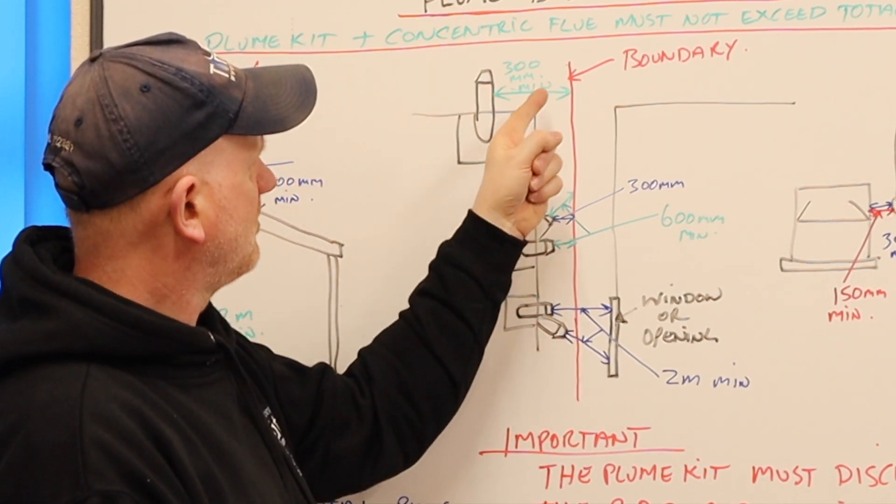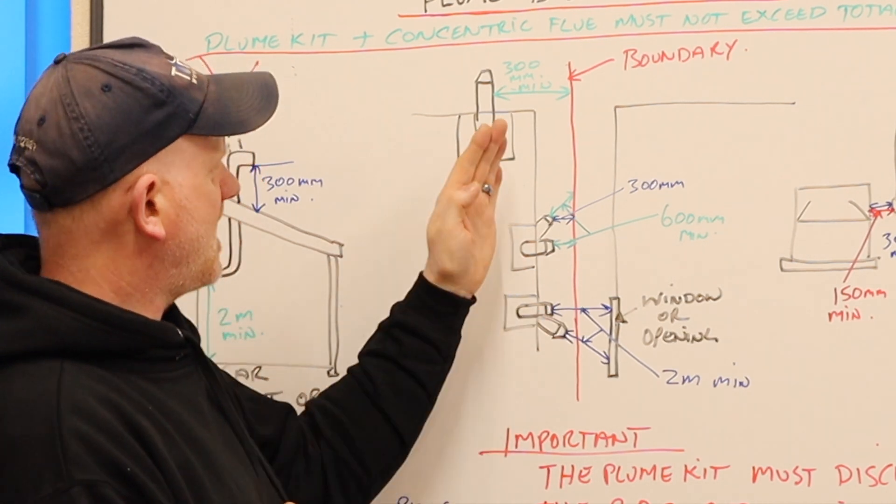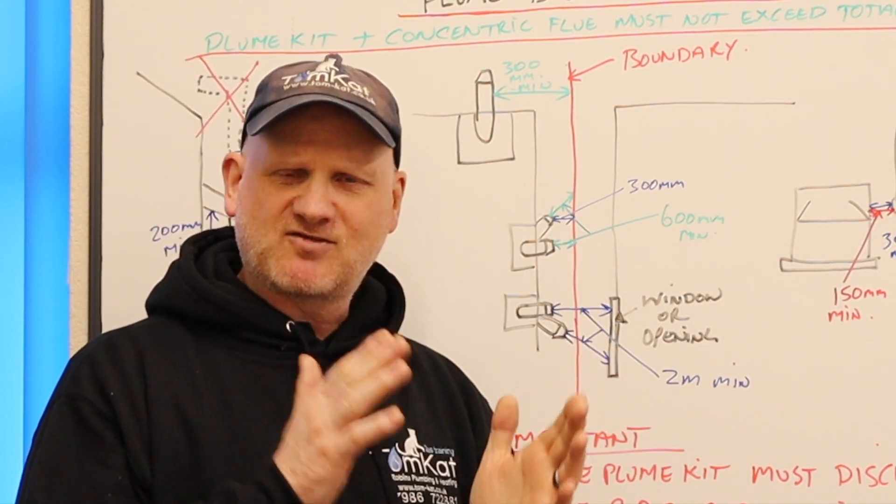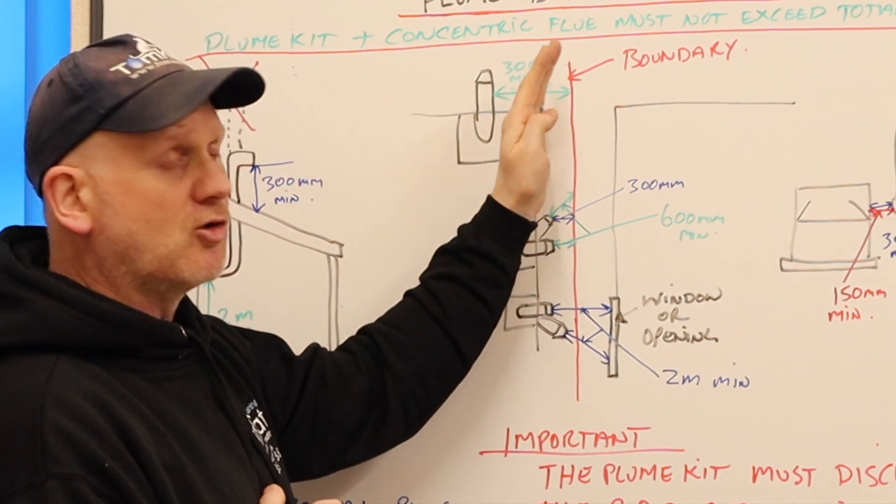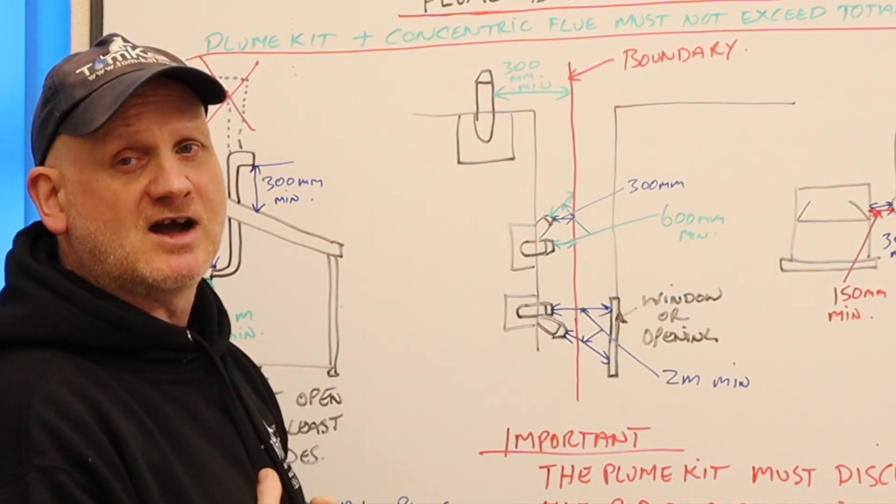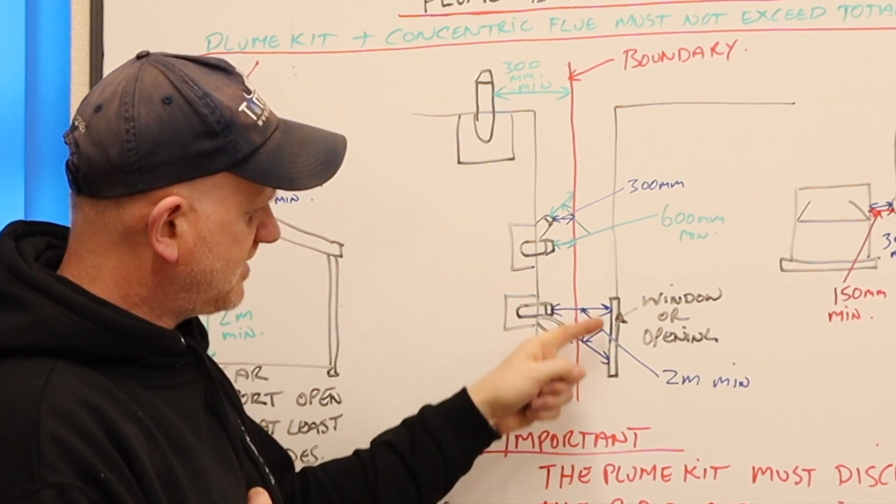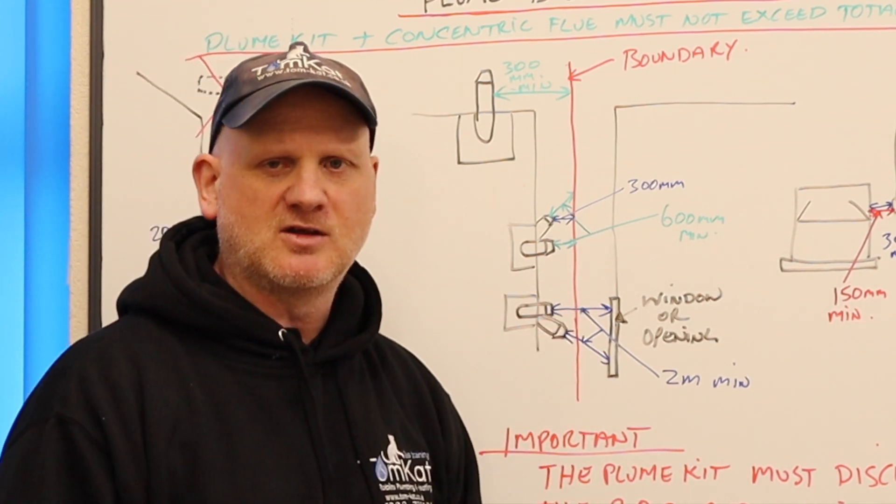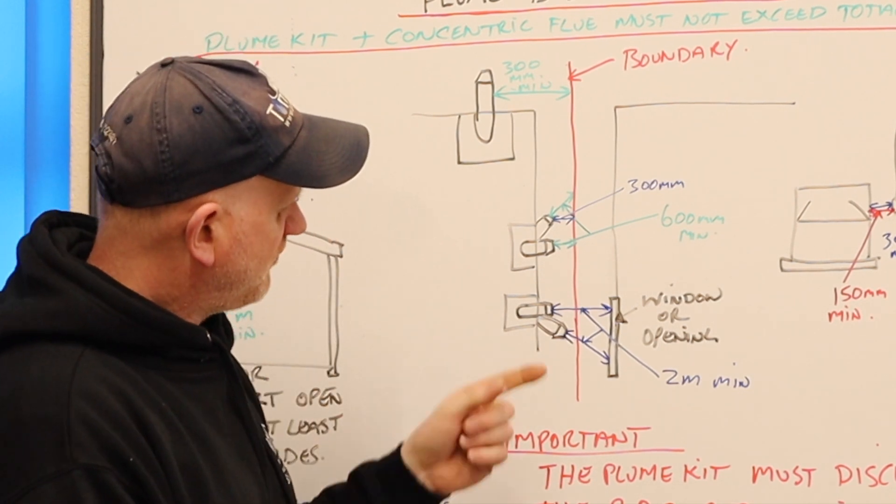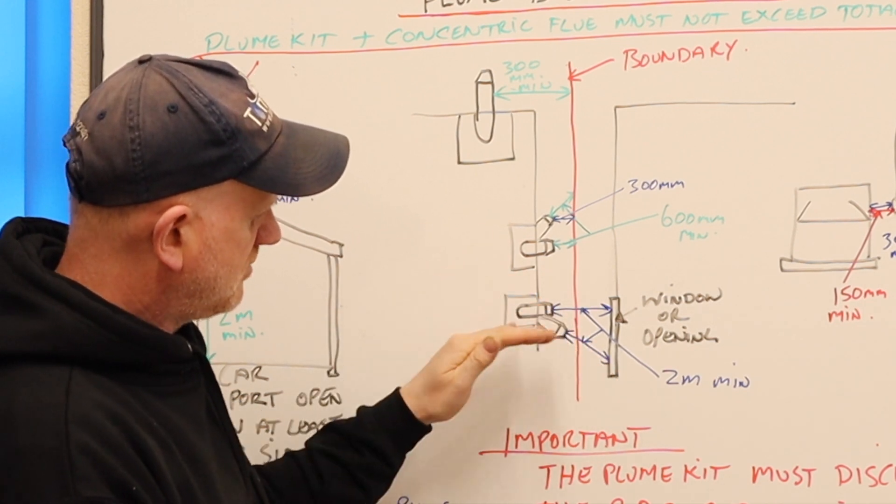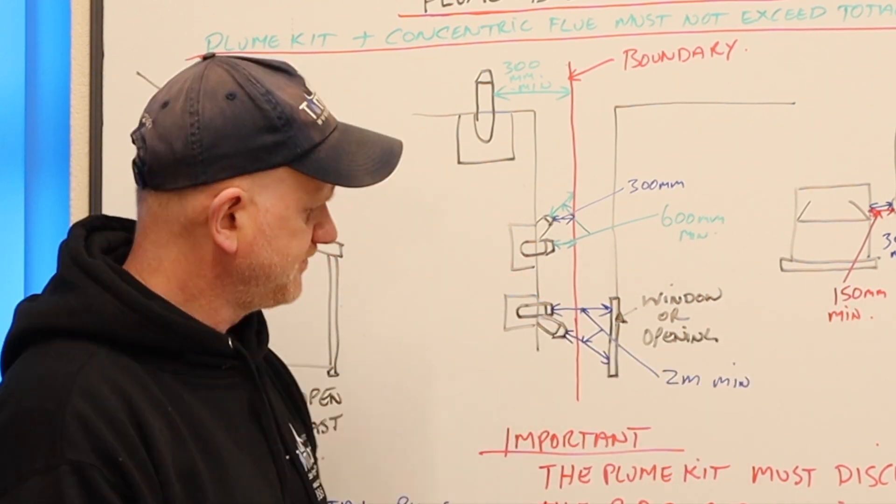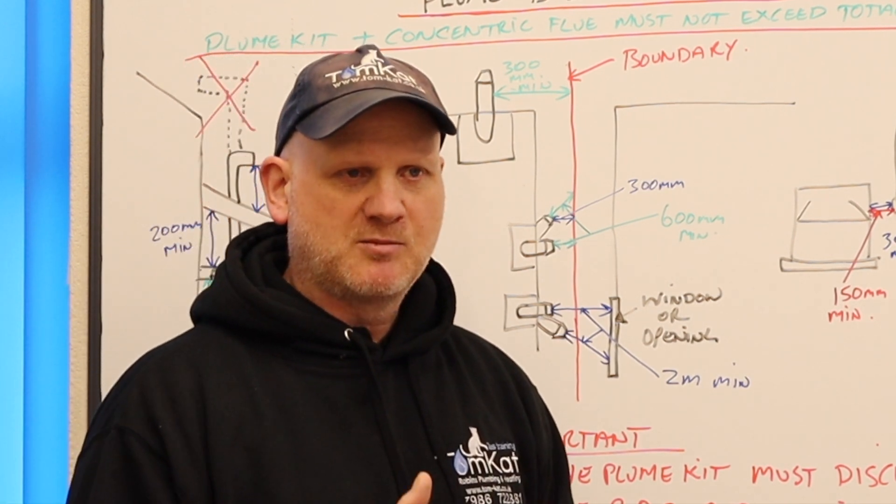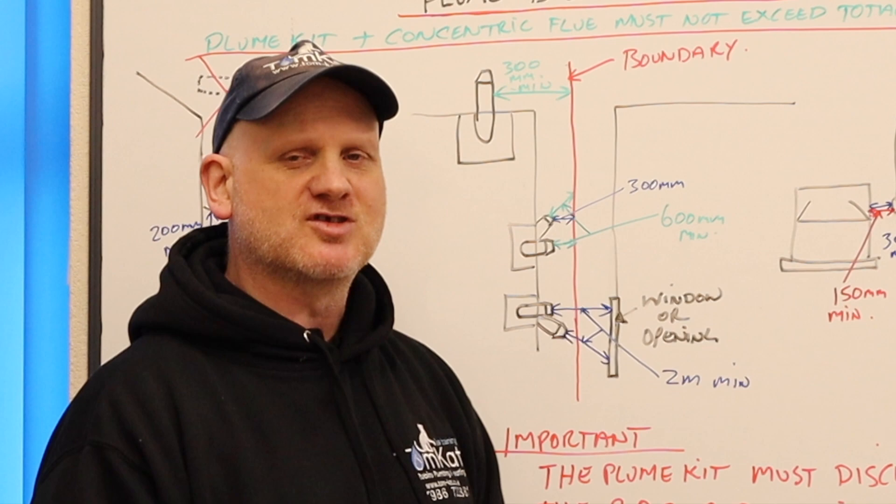Also, running parallel with the boundary we need to be 300 mil away. And again, if we're not 300 mil away we could use a plume kit going that way because basically what a plume kit does is halves your measurements. So we would only need to be 150 mil away if our plume kit was then on a 45 degree. It's pretty much like we've got down here where we're facing a window or a door or an opening into a building. We need to be two metres away according to 5440 part one. But if we have it on the 45 degree then we're still two metres away but technically we're only a metre away if we're facing it. So they're the good things what a plume kit can do. It can reduce your measurements by half but like I say only if the manufacturer says you can do.